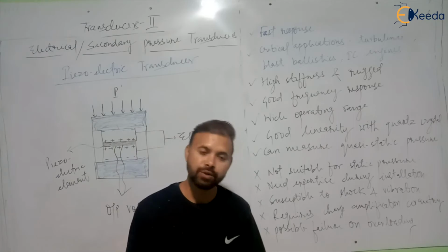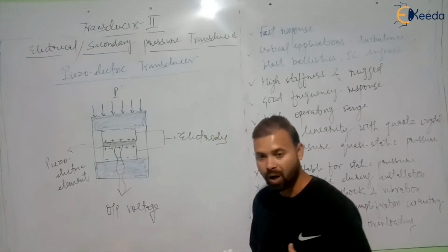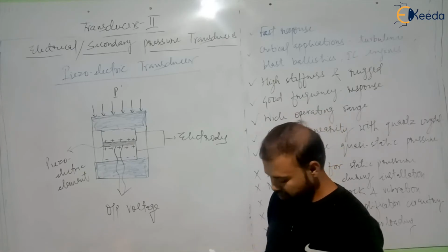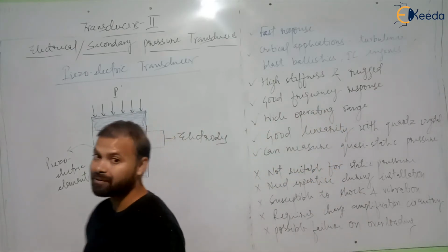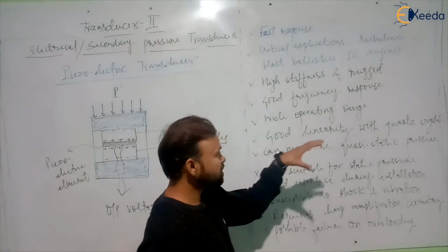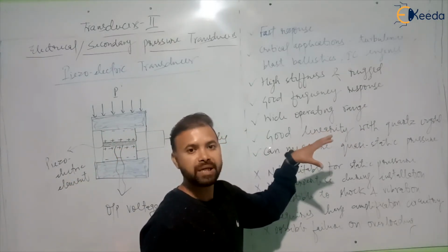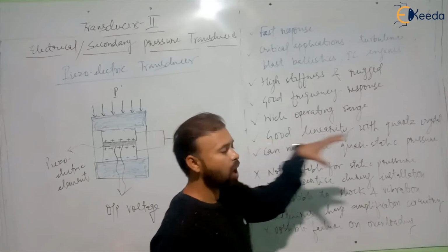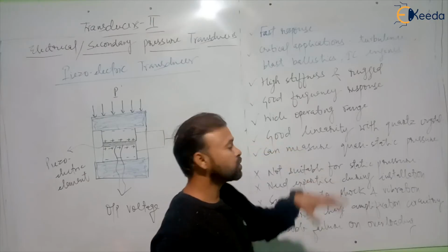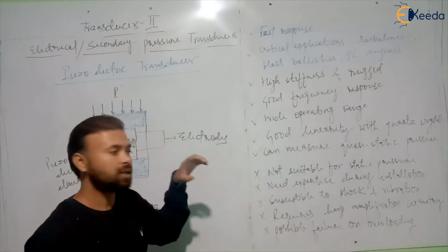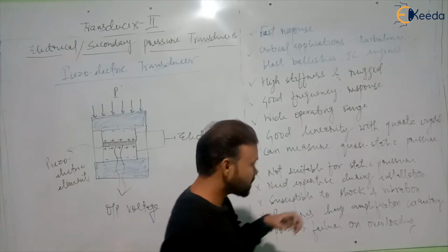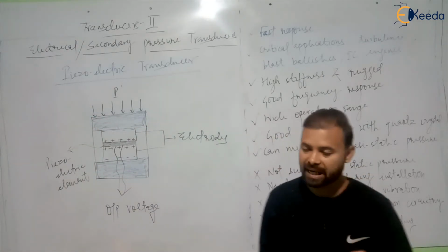And if we are using quartz crystal, quartz crystal is a piezoelectric material. There are some other synthetic materials available which have piezoelectric property. Now quartz is your natural piezoelectric material. If you are using quartz, then you have the advantage of good linearity with this quartz crystal. You can measure quasi-static pressure also.